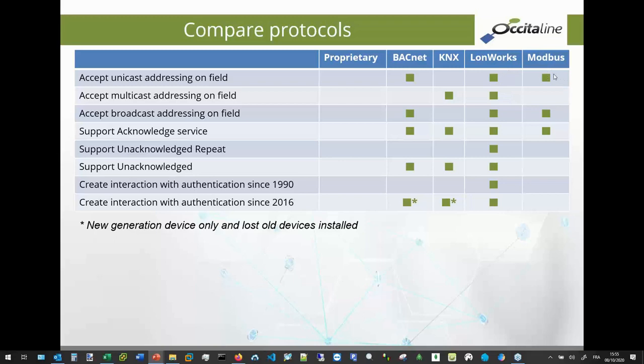If we compare protocols, we can compare different addressing modes. For example, unicast, when one lamp is connected with one push button. In BACnet, you can create a connection one-to-one. In KNX, there is no one-to-one. It exists, but not for the connection on the field. It always uses a multicast. It's the same, but we can create that with a multicast address. In LON, you can. In Modbus, it's mandatory because we have no other solution than a unicast.